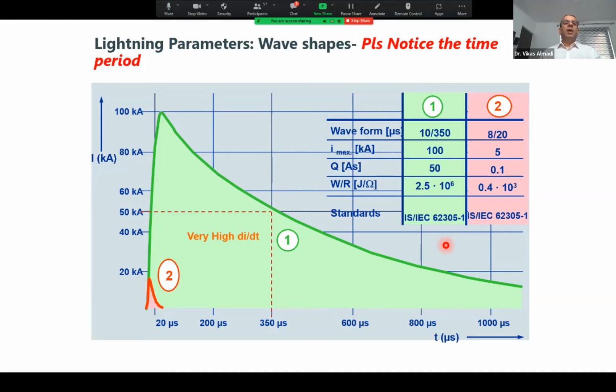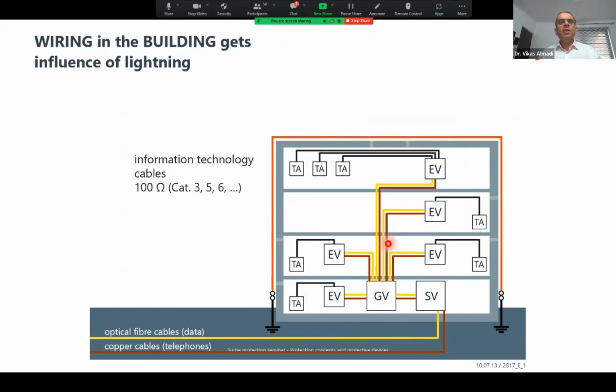And the energy content in this microsecond is in the tune of 2.5 megajoules per ohm. So consider the kind of resistance these are going to see, and the kind of heating that can be produced by these waves. These look small but are dangerous waves. So when these waves flow into a building where you have an IT system and also a power supply system, which is normally there in all buildings now, even the substation is getting digitized, you have an IT system and you have a power system.